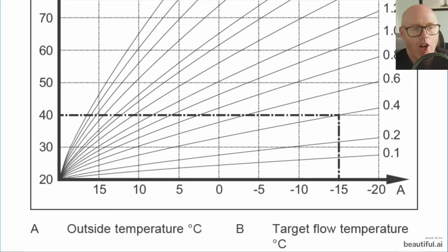Nice low and slow flow temperature especially for properties that have underfloor heating. As you can see the default setting 1.2 is very confusing in the app and it's very confusing the Senso Comfort is left by default on that. We know that this is really a boiler flow temperature because if we follow 1.2 down and we intersect at about minus three degrees, what's our flow temperature there? 55 degrees.